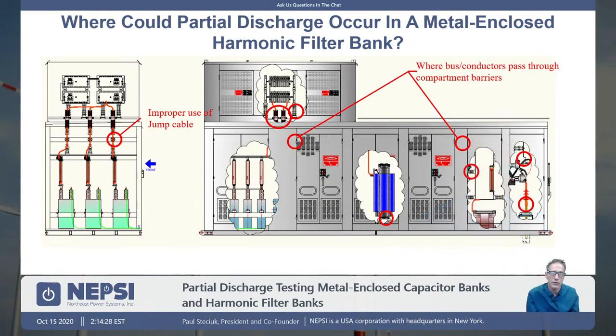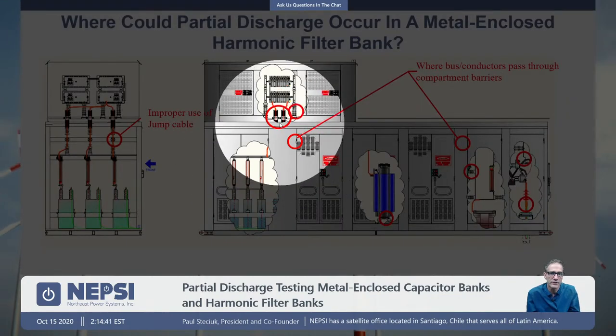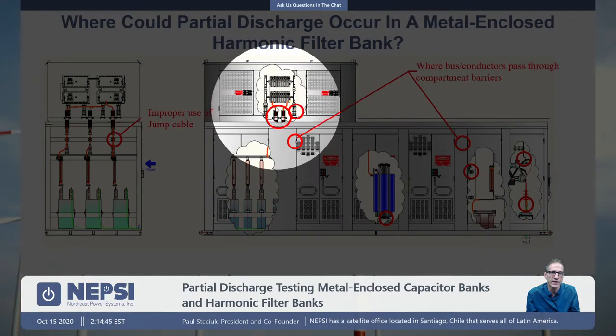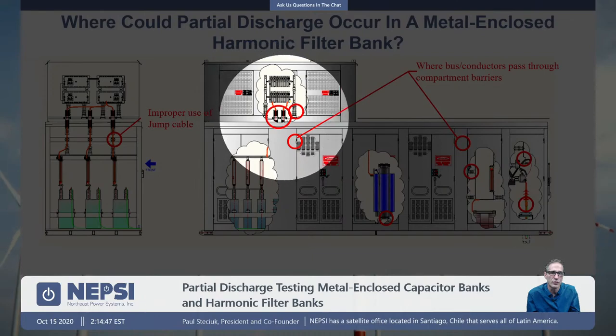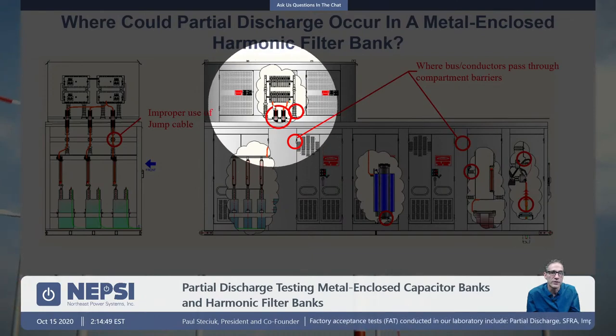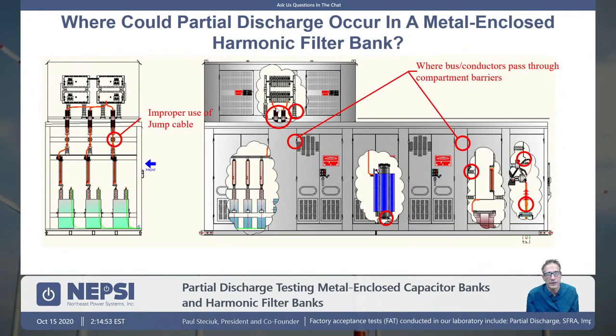When you look at the metal-enclosed system, and that's what we are, we're a metal-enclosed capacitor bank and harmonic filter bank manufacturer, so I can talk about where we would have it in our equipment. If it's a high-pass harmonic filter like we show here, we definitely would have it up in this region, where we have high-voltage conductors passing up through the roof. We use a medium voltage bushing here that is composed of both a high voltage shield and a low voltage shield, so it's a true bushing.